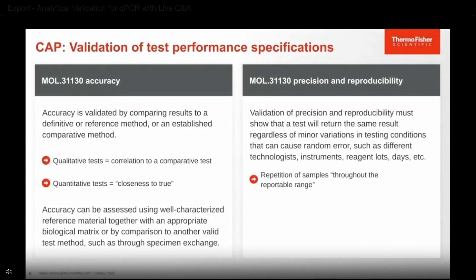Let's talk about CAP guidelines in detail. In terms of accuracy, it is validated by comparing results to a definitive or reference method or an established comparative method. For qualitative tests, we look at the correlation to a comparative test, whereas for quantitative tests we're looking for the closeness to the true results. Accuracy can be assessed using well-characterized samples in an appropriate biological matrix or by comparison to another valid test method, such as a specimen exchange.